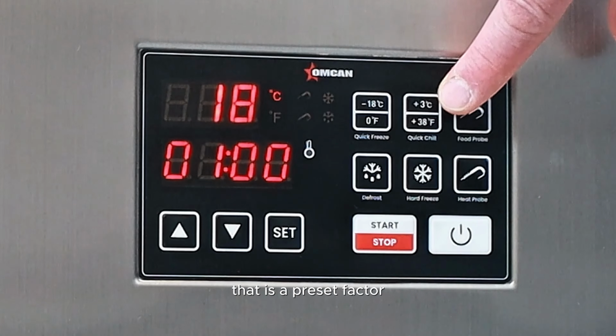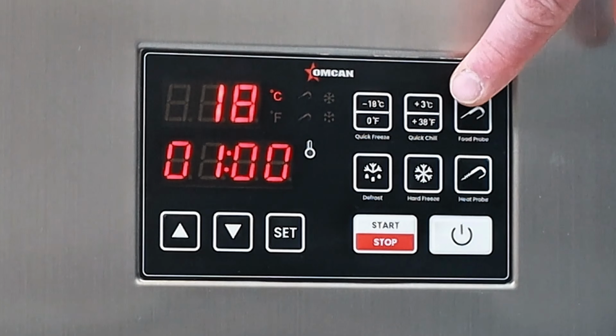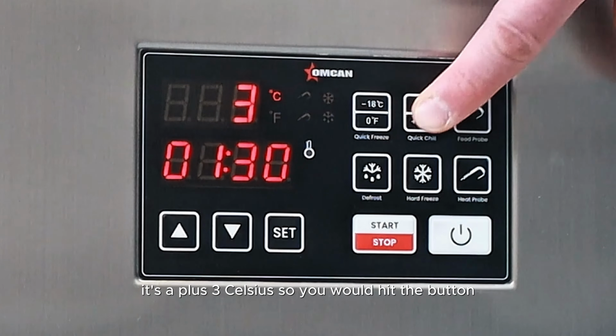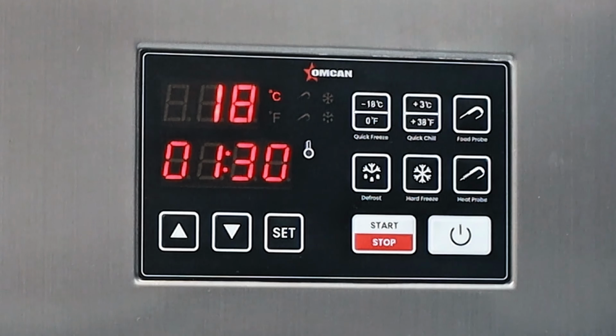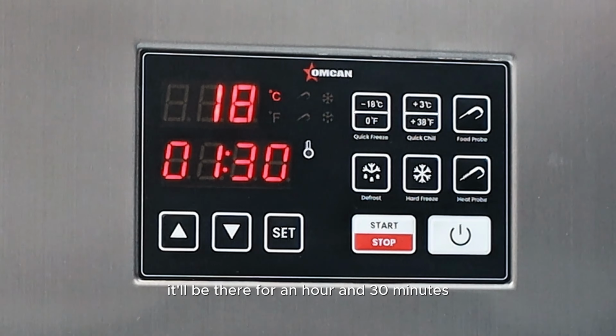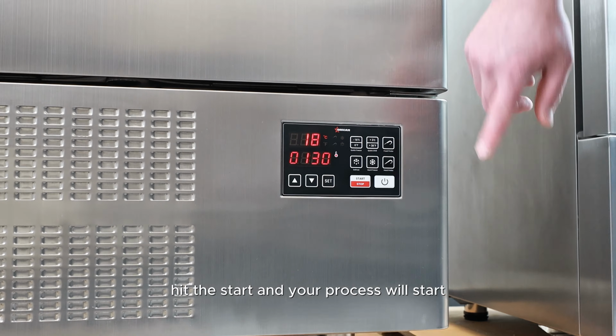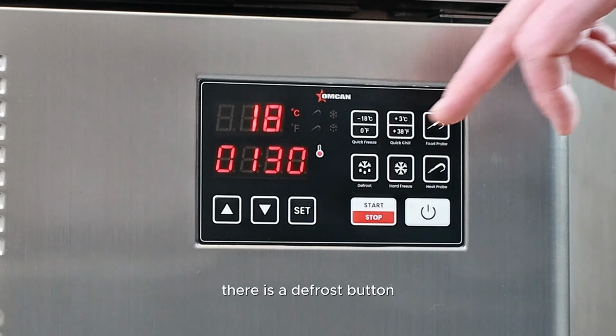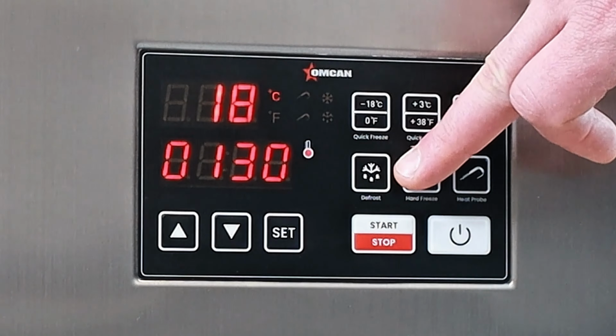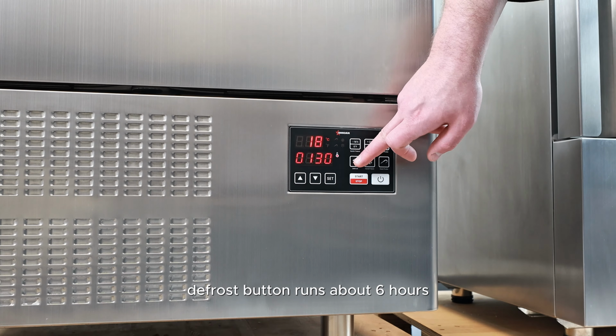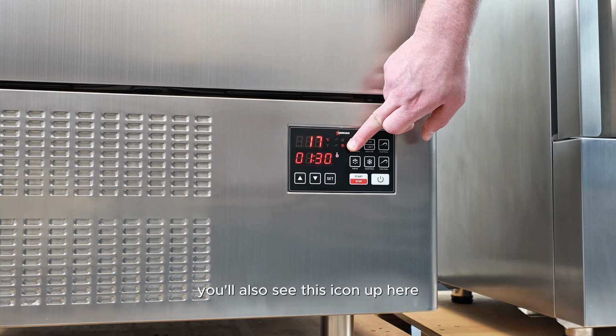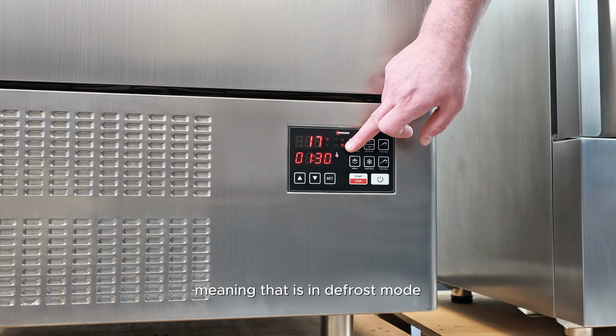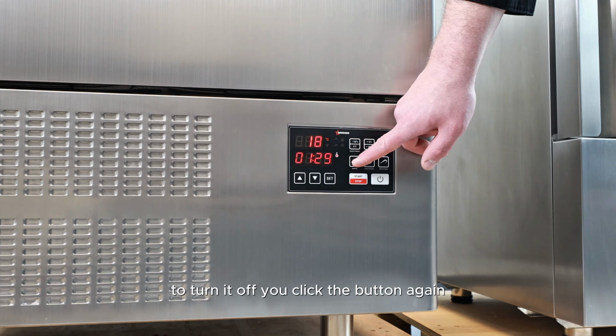There is also a quick cool option. That is a preset factor. It's a +3 Celsius, so you would hit the button. It'll be there for 1 hour and 30 minutes. Hit the start, and your process will start. There is a defrost button. Defrost button runs about 6 hours. You'll also see this icon up here, meaning that is in defrost mode. To turn it off, you click the button again.